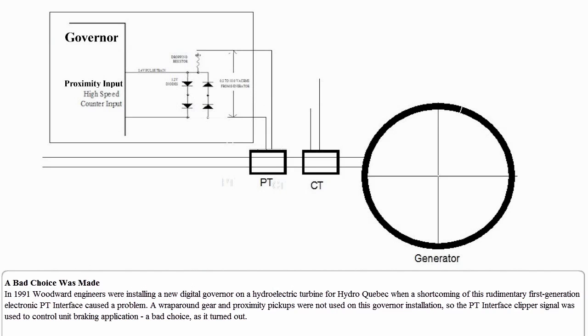In 1991, Woodward engineers were installing a new digital governor on a hydroelectric turbine for Hydro-Quebec when a shortcoming of this rudimentary first-generation electronic PT interface caused a problem. A wraparound gear and proximity pickups were not used on this governor installation, so the PT interface clipper signal was used to control unit braking application. A bad choice, as it turned out.